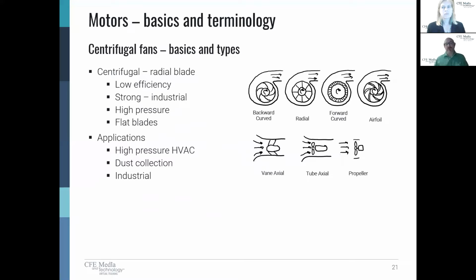A more useful style of fan is a centrifugal fan. Now, unlike the axial fan, in which air is moving parallel to the shaft, in a centrifugal fan, air is actually moving perpendicular. So if we take a look at these drawings that I very artistically created, you can see that air is flowing into the screen, right? Into the screen, into the center hub, and then it's being turned so it's spreading out perpendicular, or radially.